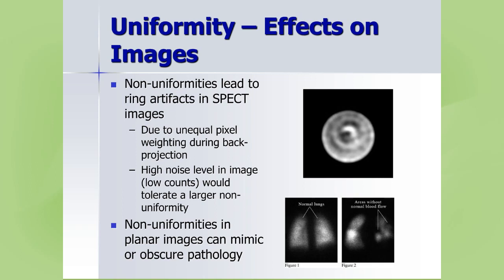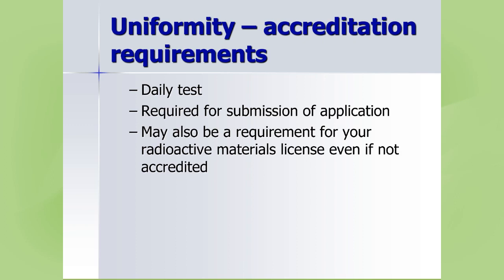For accreditation requirements: uniformity is a daily test required by most state regulations and accreditation bodies. You may need to submit pictures or policies and procedures. Check your radioactive materials license for documentation requirements — in Colorado, for example, the state asks to see these records whether you are accredited or not.